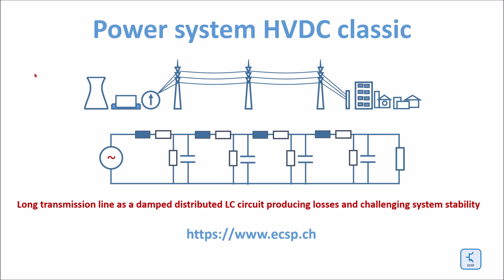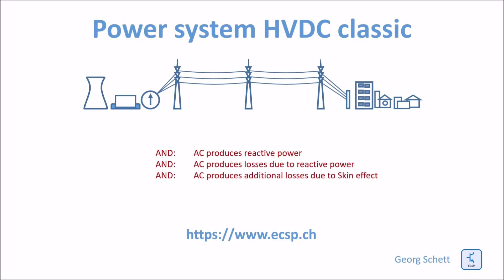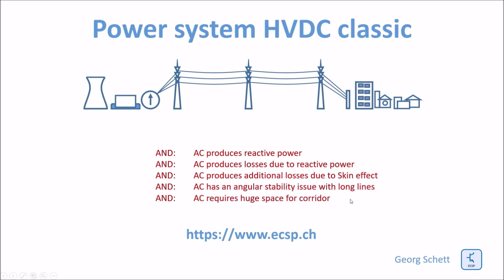Very long transmission lines above around 1000 km challenge system stability. AC produces reactive power and losses due to reactive power. It produces additional losses due to the skin effect — an effect which reduces the cross-section of a conductor utilized at higher frequencies. AC also has angular stability issues with long lines and requires huge space for the corridors.